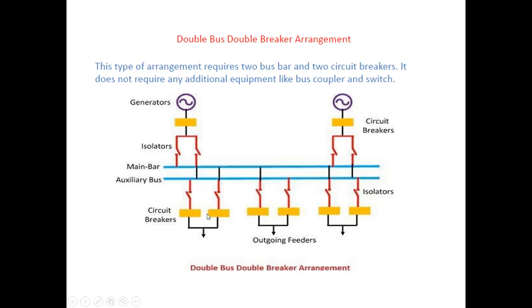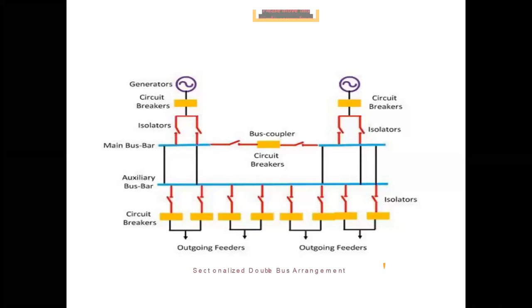With two bus bars and two circuit breakers, the cost increases. The double bus double breaker scheme is the most expensive method, as it uses two circuit breakers and two isolating switches per circuit. A sectionalized version using bus coupler circuit breakers also exists. If any fault occurs in one section, the circuit breaker trips, the isolator is opened for maintenance, and the outgoing feeders remain connected — maintaining continuity of power supply.